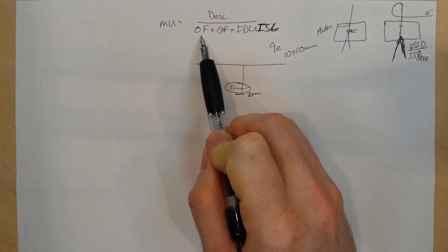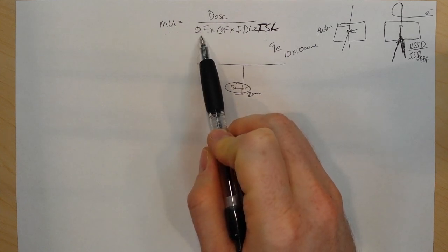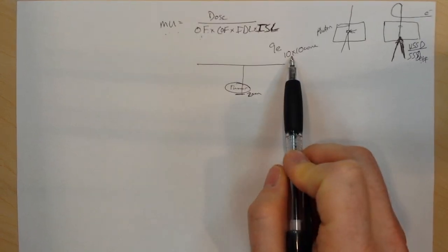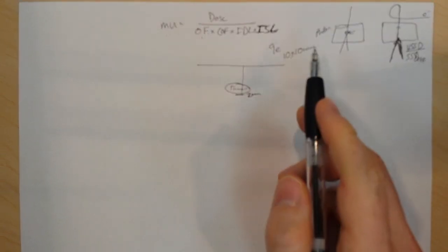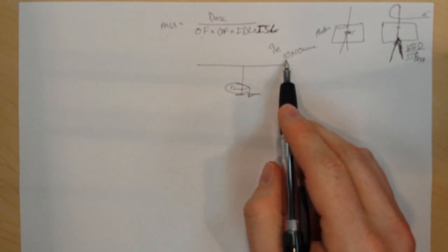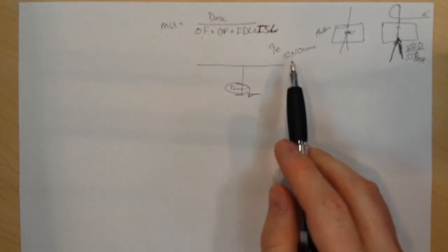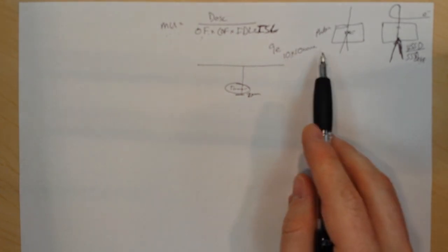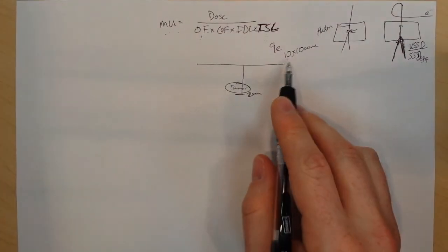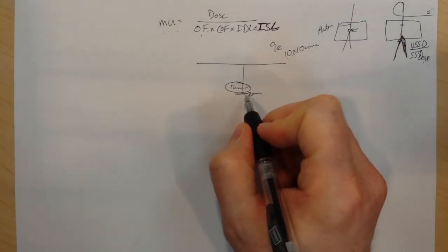Oh, I should make a comment. Typically, departments have a standard cone size that equals 1.0 for their output that they do their calibration for, just like photon energies. Normally, 10 by 10 is standard for electrons, although it varies by institution. Some institutions do 15 by 15. A lot of times, you won't see very much change between the outputs for a 10 by 10 and a 15 by 15 cone size. In fact, I encourage you to look at your different output factors for the electrons, and you'll notice that there's not a huge difference between them, just a few percent.